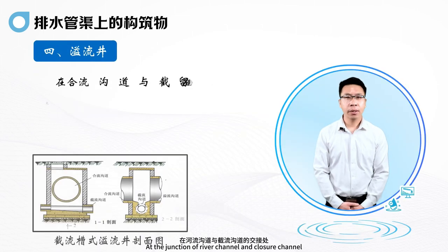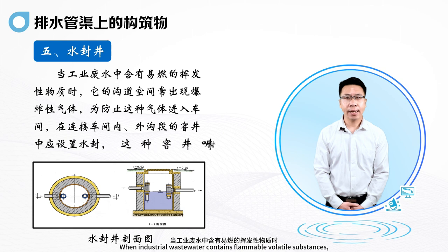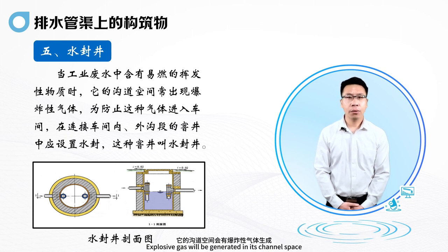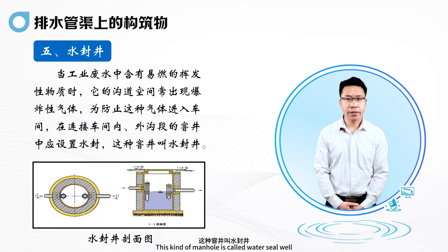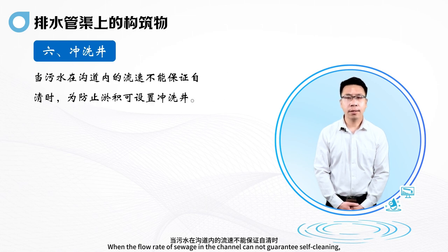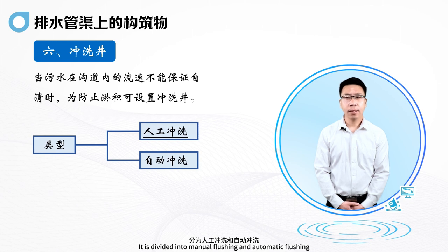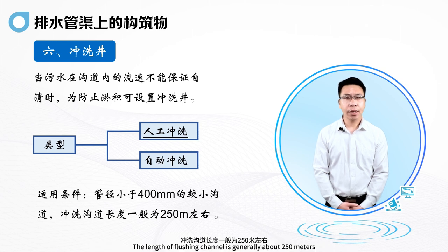Fourth, overflow well. At the junction of river channel and closure channel, overflow wells are set up to complete the functions of interception and overflow. Fifth, water sealed well. When industrial wastewater contains flammable volatile substances, explosive gas will be generated in its channel space. To prevent this gas from entering the workshop, a water seal shall be set in the inspection well connecting the inner and outer ditch sections of the workshop — this is called a water seal well. Sixth, flushing wells. When the flow rate of sewage in the channel cannot guarantee self-cleaning, flushing wells can be set up to prevent siltation. There are two types: manual flushing and automatic flushing. Applicable conditions: generally smaller channels with pipe diameter less than 400 millimeters; the length of flushing channel is generally about 250 meters.